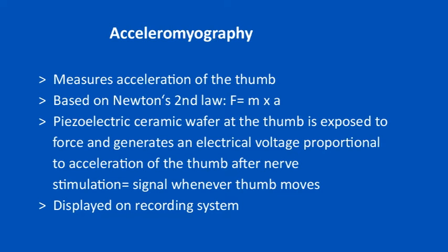Here we use a piezoelectric ceramic wafer sensor at the thumb, which is exposed to force and generates an electrical voltage which is proportional to acceleration of the thumb after the nerve stimulation. This signal occurs whenever the thumb moves. It is displayed on the recording system.